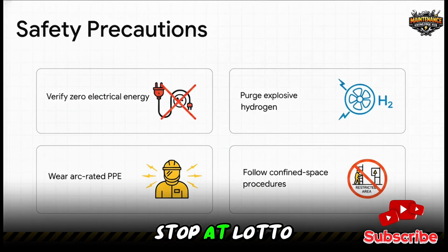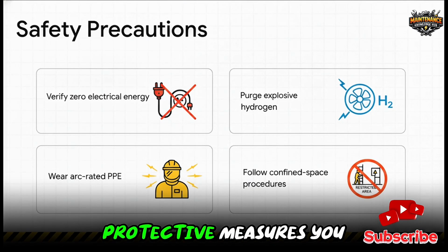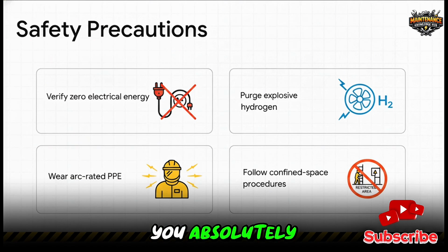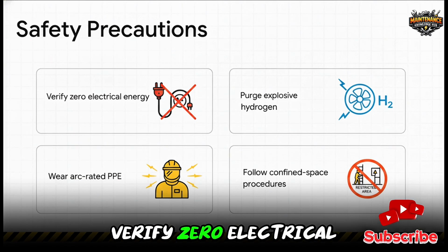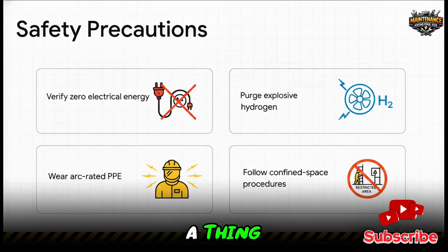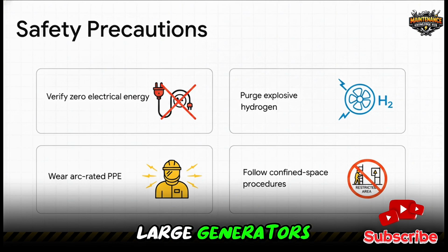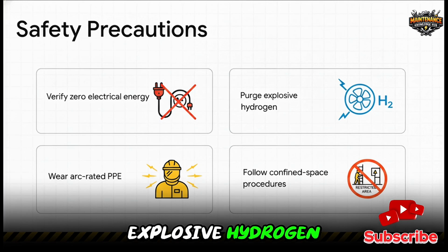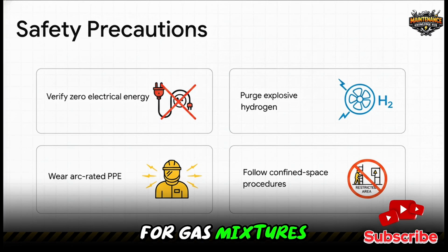But it doesn't stop at LOTO. There are several vital protective measures you have to follow. You absolutely must physically verify zero electrical energy before touching a thing. And because these large generators use hydrogen gas for cooling, which we'll talk about more in a bit, you have to safely purge that explosive hydrogen and rigorously test for gas mixtures before you even think about cracking open the casing. You're wearing standard PPE, right?